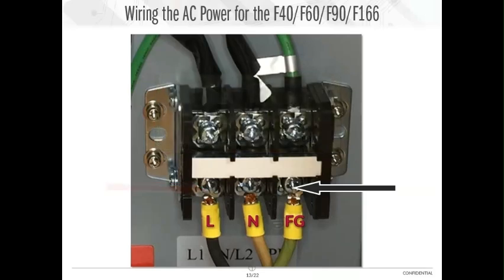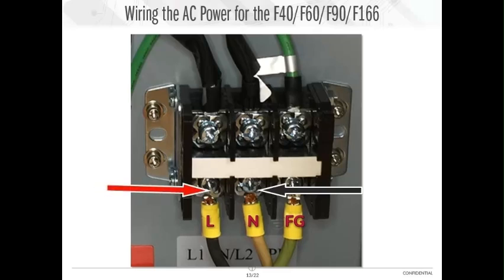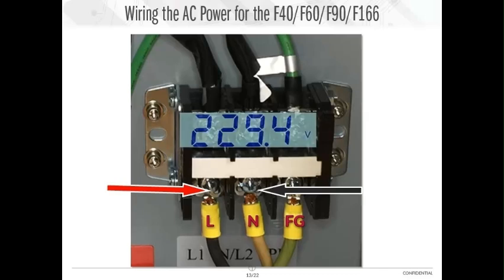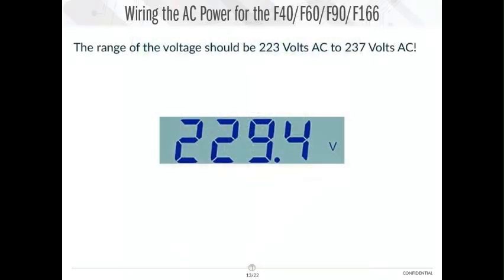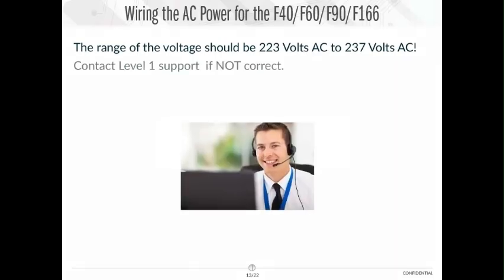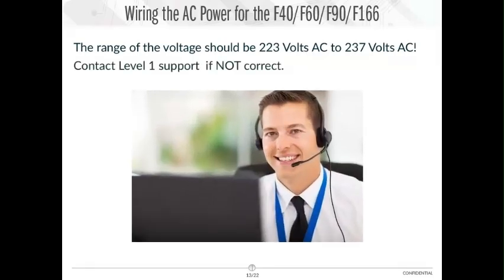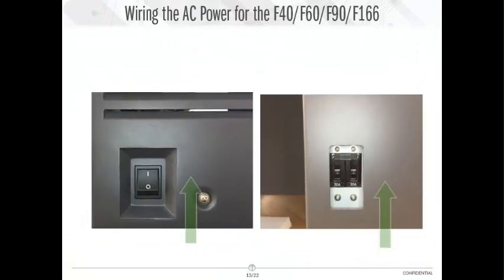Now, take the black probe from your meter and place it on the white wire, this is the terminal marked N, and then place the red probe on the terminal marked L, this is the black wire, and read the voltage at these 2 points. The voltage should be about 230 volts AC, plus or minus 3%. This is a range of approximately 7 volts. The voltage should be between 223 volts to 237 volts. If the voltage does not fall within these parameters, contact Level 1 support. Once you have verified that the voltages are correct, you may turn on the power to the printer as outlined in the installation section of the manual.